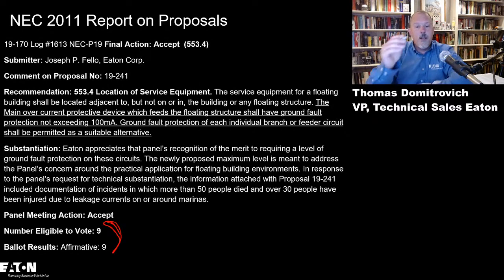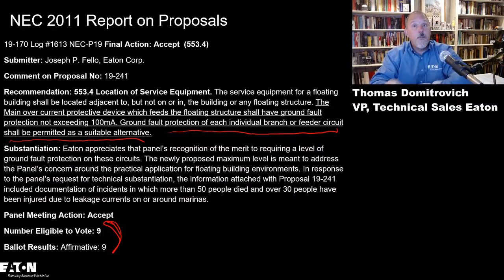That required 100 milliamps at the service, and what we did was say ground fault protection of each individual branch or feeder shall be permitted as a suitable alternative. So our thought process was you can either put it on the main, or every feeder gets 100 milliamps or less. The first issue that came up was people said nobody makes a 100 milliamp device, but it says not exceeding 100 milliamps. So that's sort of where we were.